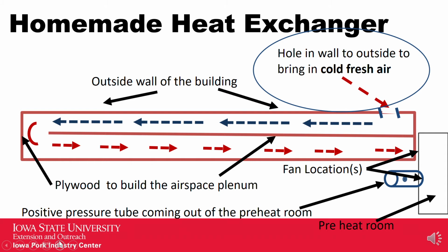And you may want to put a fan forcing air into the preheat room. That's a room with a heater. Or you can put a fan pushing out of the preheat room into what I call the air distribution tube. You'll see what that looks like on the next slide. It's a black field tile in this example that's engineered with holes cut out to manage uniform air distribution in the room.